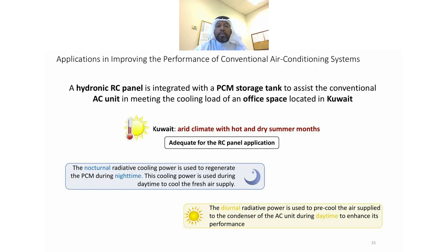Before going into details, let's look briefly at the mechanism of radiative cooling during the day and night. During the night, the nocturnal radiative cooling power is used to regenerate or solidify the phase change material, and this saved cooling power is used later during the day to cool the fresh air. During the day, the diurnal radiative cooling power is used to pre-cool the air supply to the condenser of the AC unit, enhancing its performance. So we use both daytime and nighttime cooling in this system.